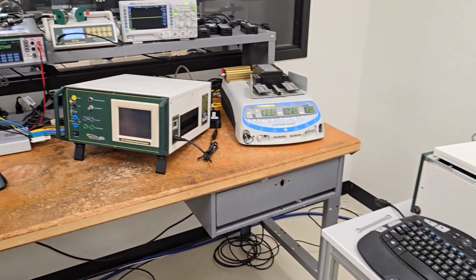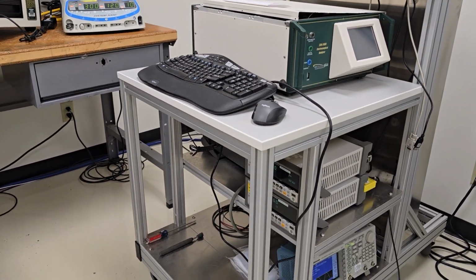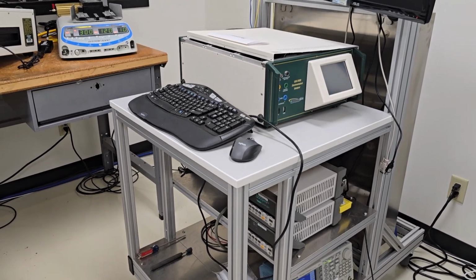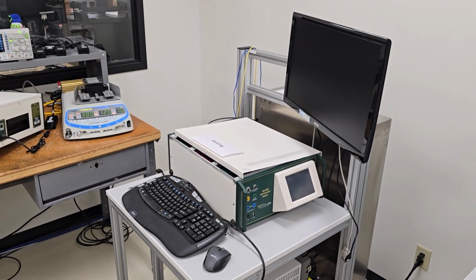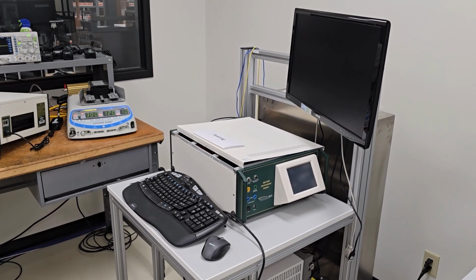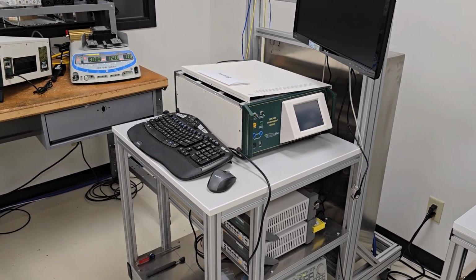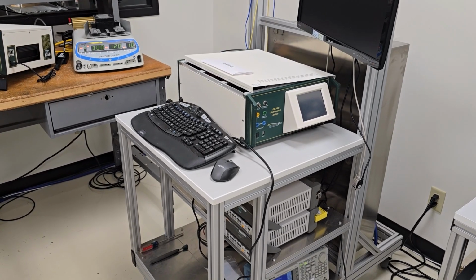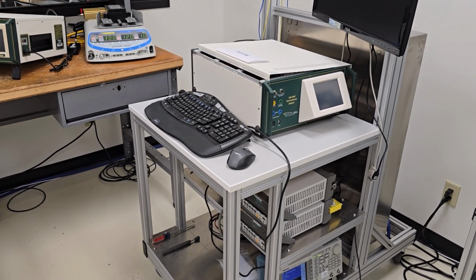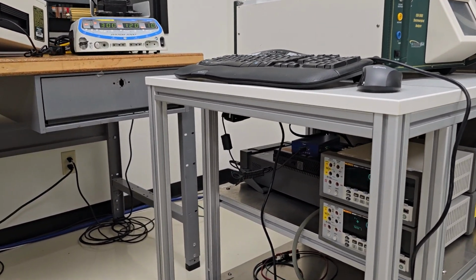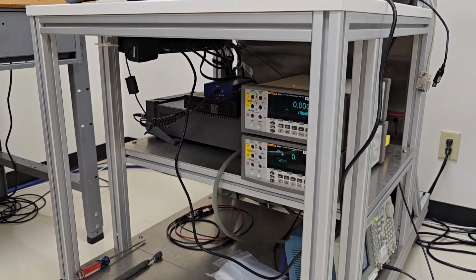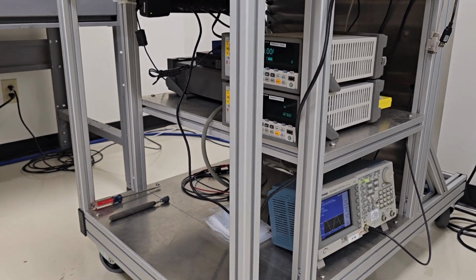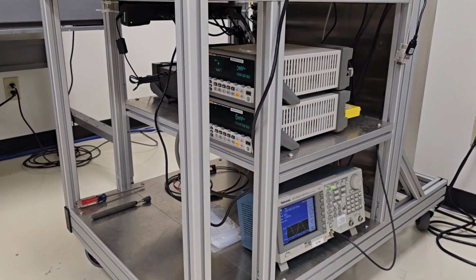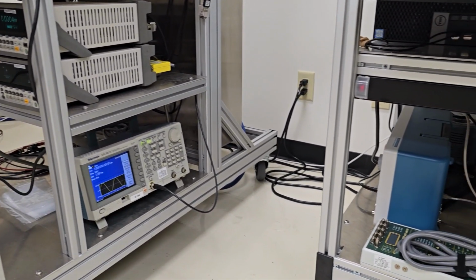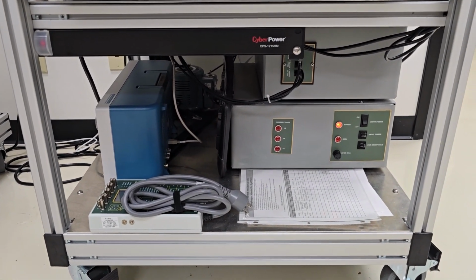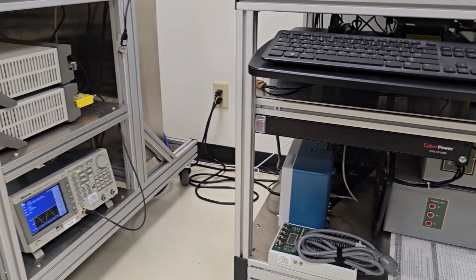And then this rig over here, this rig is the reason we don't do on-sites for ESUs. So all of that equipment is required to do a true calibration on an ESU, 2050, 2400, 2300. There are thermal voltage converters in there, switch boxes, a signal generator, a calibrated DC source, multiple multimeters. And this system allows us to do that calibration autonomously. We can sweep all of the frequencies across the operating range. We can sweep the amplitudes, and that's just something you really can't do in the field.